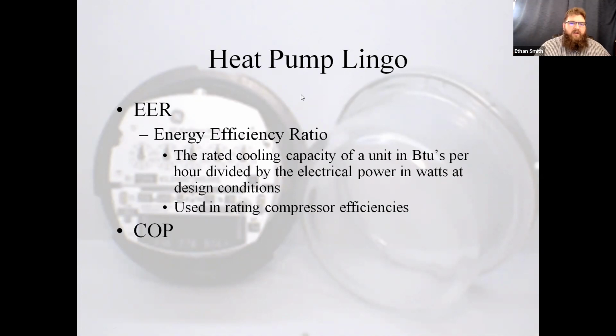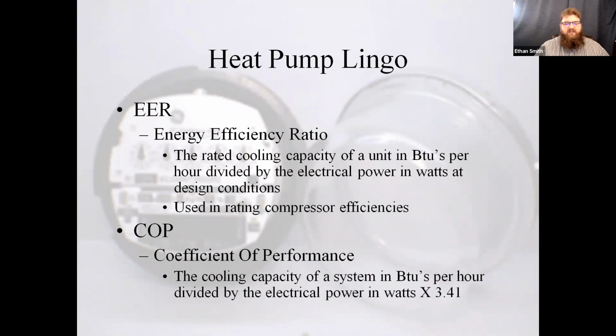COP is a coefficient of performance. This is also a measure of efficiency. It's generally referred to as the cooling or heating capacity of a system in BTUs per hour divided by electrical power. These two kind of go hand in hand, but they're not quite the same. EER is at design conditions. COP is the cooling capacity. It's basically the same thing, but it's at any set of conditions that you set. So we'll look at some performance charts in a little bit where we'll be able to calculate COPs at different outdoor temperatures and different indoor temperatures.